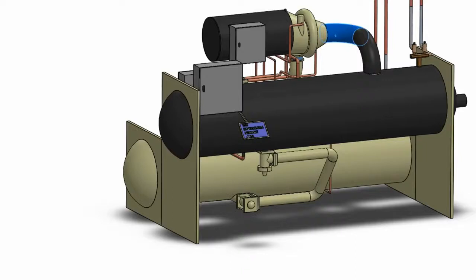If liquid gets in there, too much liquid, it will break the compressor. The compressor does not like liquid entering it. So keeping the right amount of superheat entering the compressor keeps your compressor and your chiller healthy, and also allows it to run in a much more efficient manner.